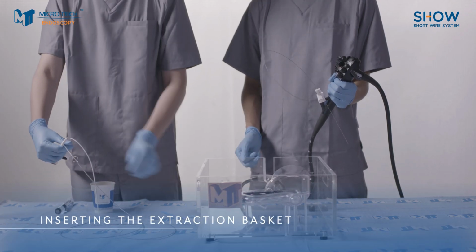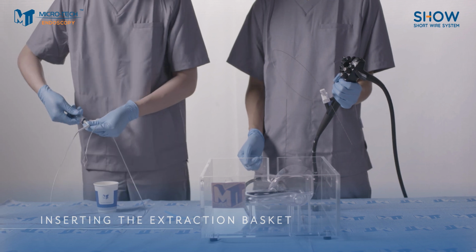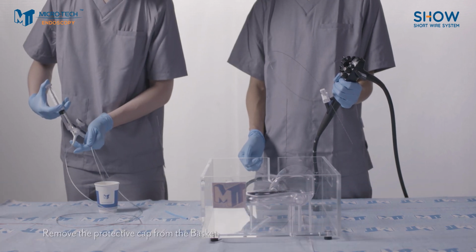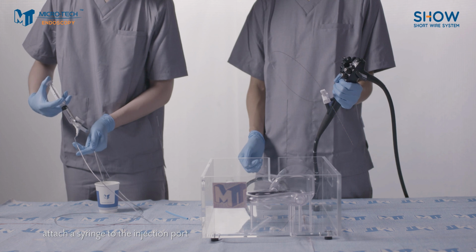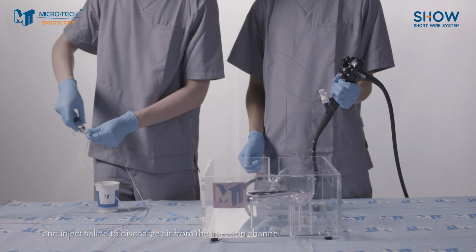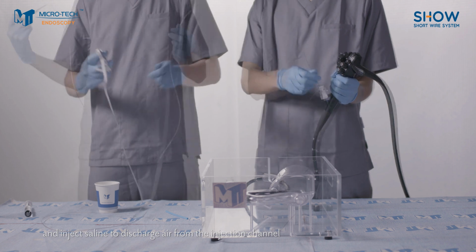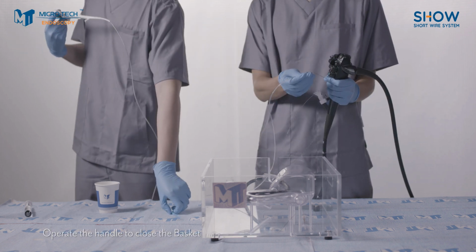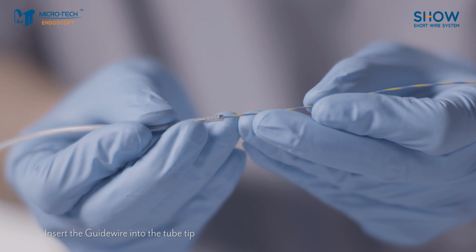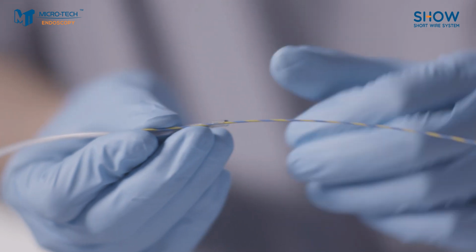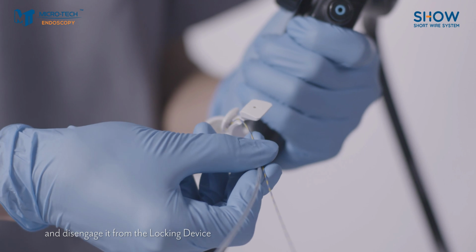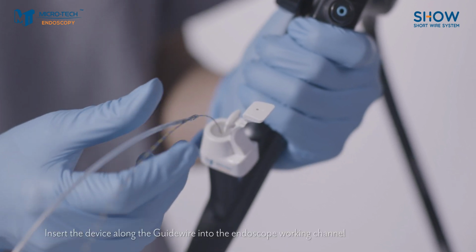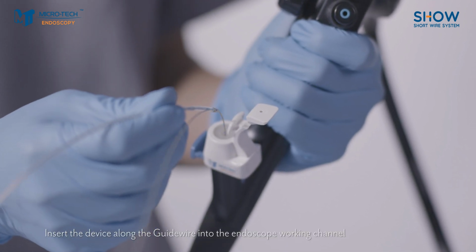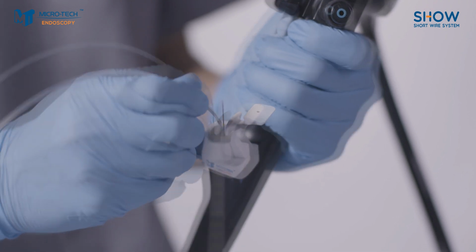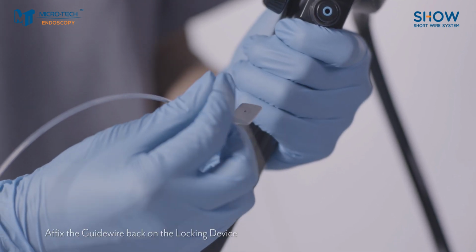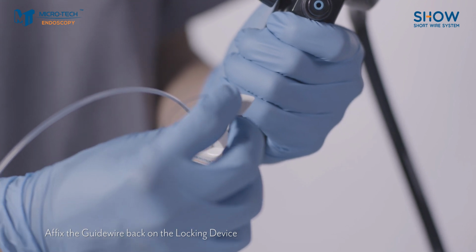Inserting the extraction basket. Remove the protective cap from the basket, attach a syringe to the injection port, and inject saline to discharge air from the injection channel. Operate the handle to close the basket. Insert the guide wire into the tube tip and disengage it from the locking device. Insert the device along the guide wire into the endoscope working channel. Affix the guide wire back on the locking device.